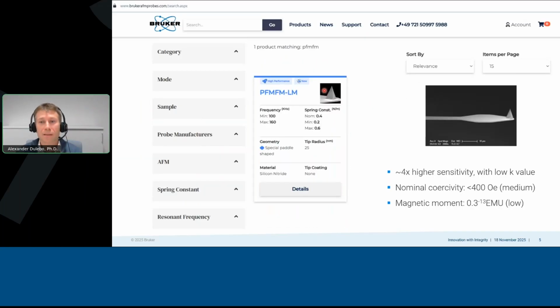And as I said, we can really benefit from using a dedicated probe, and we already have a dedicated probe for PeakForce Tapping MFM, and that's the MFM LM. This probe is way softer, almost 10 times softer than the traditional MESP probe, so it gives higher sensitivity. And of course, it's also a sharper probe.